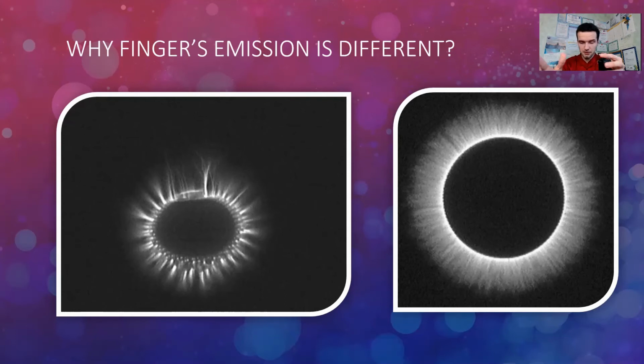Then the images will be stable and reproducible. So whenever you see irregularities of the metal cylinder, first of all, clean the surface of the metal cylinder and clean the surface of the Biowell device, or any other GDV device if you're using other models.